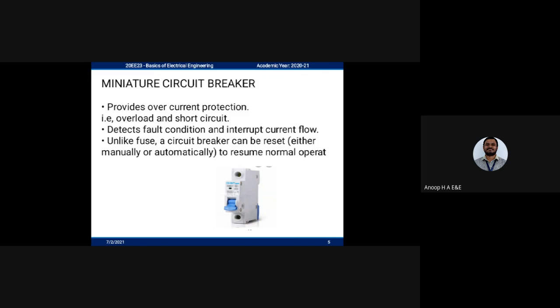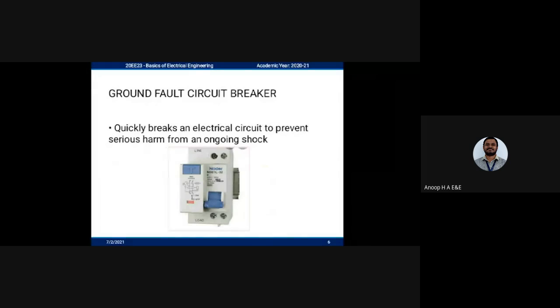And the next one is the MCB, meaning miniature circuit breaker. It is used to safeguard homes from overload due to its capacity to handle large amounts of electricity. They are much more reliable and safer than the fuse. It provides equal distribution of electrical energy across all the devices. And the ground fault circuit breaker outlet stops any electrical current leakage. It cuts it off before it has a chance to spark an electrical fire.